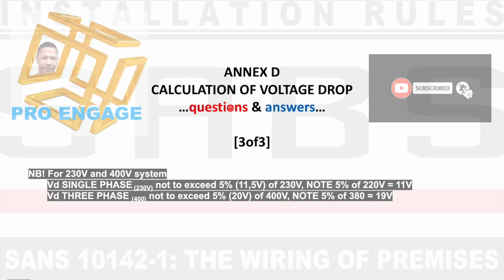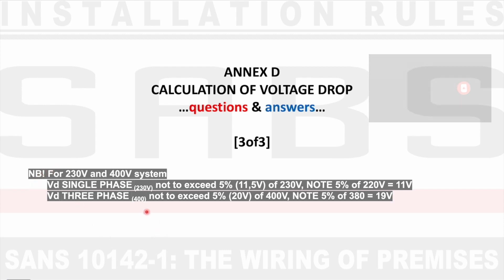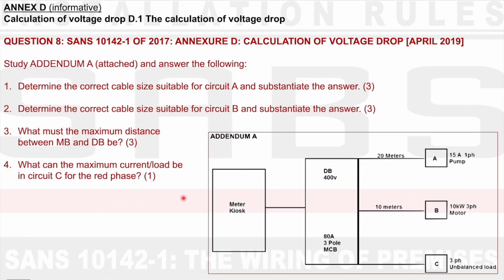Hi there, welcome to Annex D, Calculation of Voltage Drop. For single phase we use 230 volts and in three phase we use 400 volts. Now once again, 5% maximum allowable voltage drop of 230 volts is 11.5 volts and it would be 20 volts for 400 volts. For 380 it would be 19 volts and 220 volts it would be 11 volts.